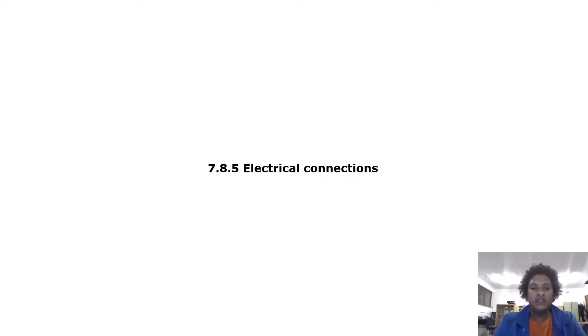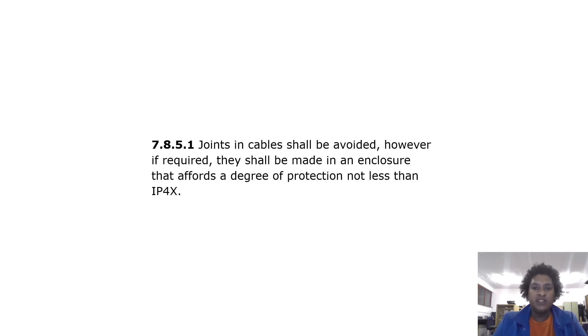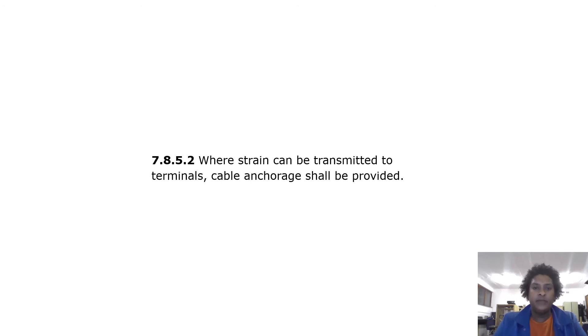Electrical connections — joints in cables: joints in cables shall be avoided; however, if required, they shall be made in an enclosure that affords a degree of protection not less than IP4X. Where strain can be transmitted to terminals, cable anchorage shall be provided.